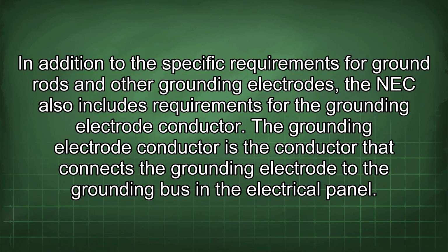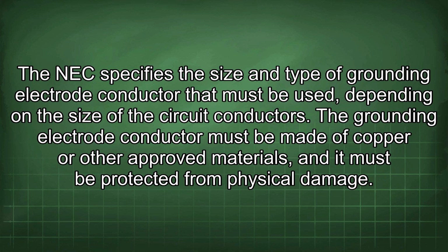In addition to the specific requirements for ground rods and other grounding electrodes, the NEC also includes requirements for the grounding electrode conductor. The grounding electrode conductor is the conductor that connects the grounding electrode to the grounding bus in the electrical panel. The NEC specifies the size and type of grounding electrode conductor that must be used, depending on the size of the circuit conductors.